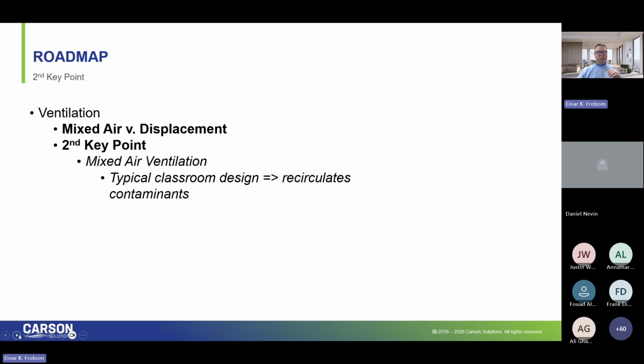So key point number two, which is understanding the difference between a mixed air environment and a displacement ventilation approach. And mixed air ventilation is doing exactly what its name implies. It's mixing the air. That could be a fan coil, a unit vent, water source heat pump, VRF, over rooftop, etc. And the point I'm conveying is that more outside air by itself, or more filtered air, more clean equivalent air, isn't the sole point of delivering better indoor air quality. How air moves through a room is critically important for the purposes of better indoor air quality.